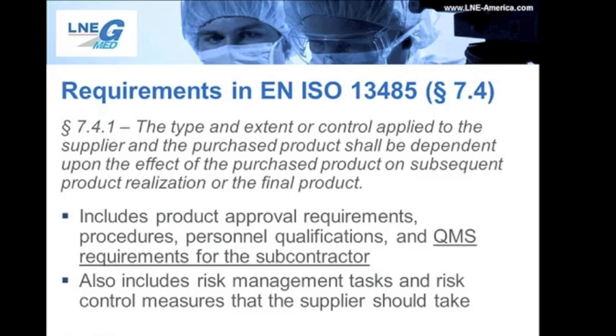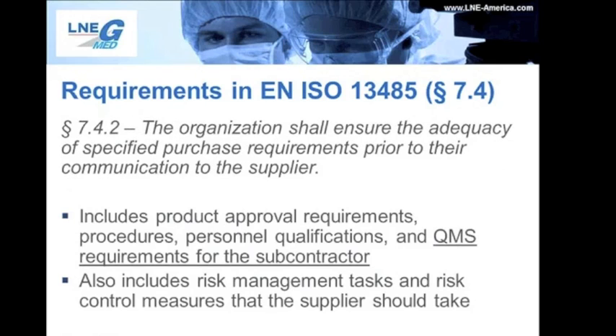Section 7.4.2 states that the organization shall ensure the adequacy of the specified purchase requirements prior to their communication with their supplier. So what does this mean? Essentially, this means that the manufacturer should make sure, on its end, that it knows all of the specifications the subcontractor needs to meet before communicating them with the subcontractor. It's the manufacturer's responsibility to make sure the supplier or subcontractor is meeting its requirements.